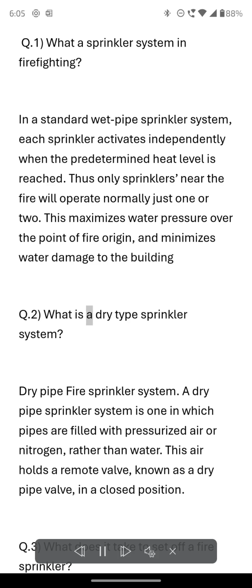Q.2. What is a dry type sprinkler system? Dry pipe fire sprinkler system. A dry pipe sprinkler system is one in which pipes are filled with pressurized air or nitrogen rather than water. This air holds a remote valve, known as a dry pipe valve, in a closed position.